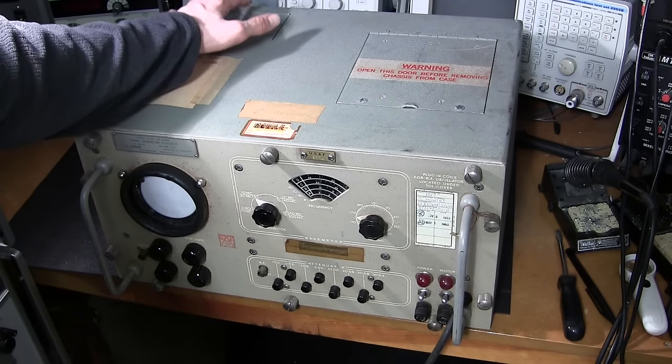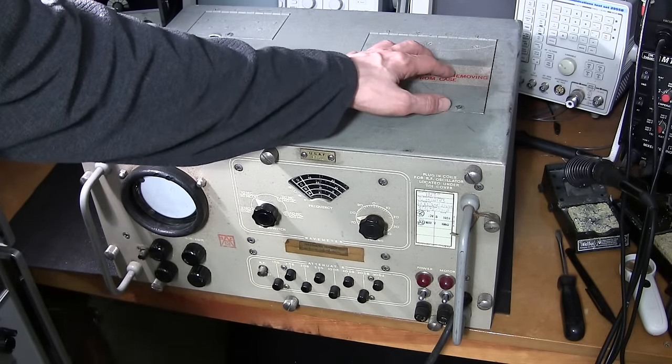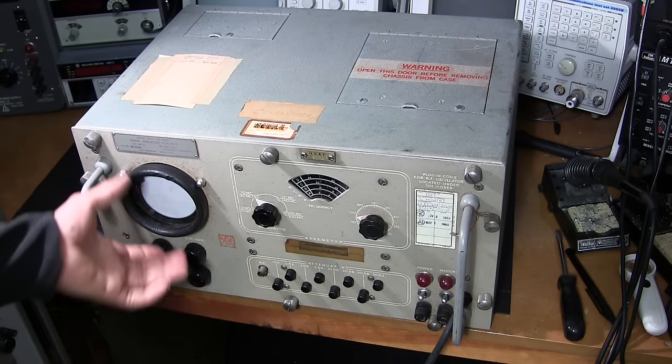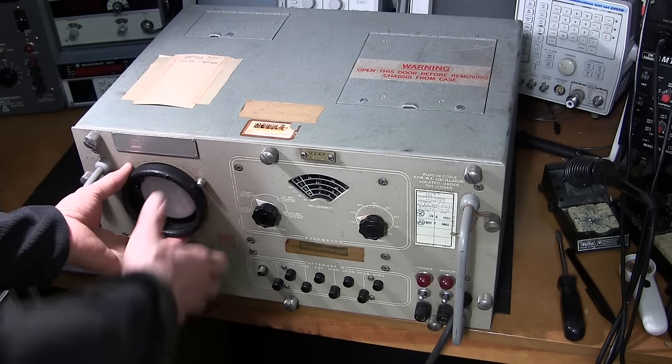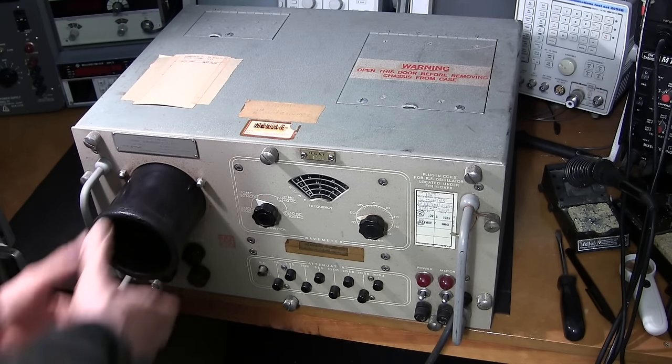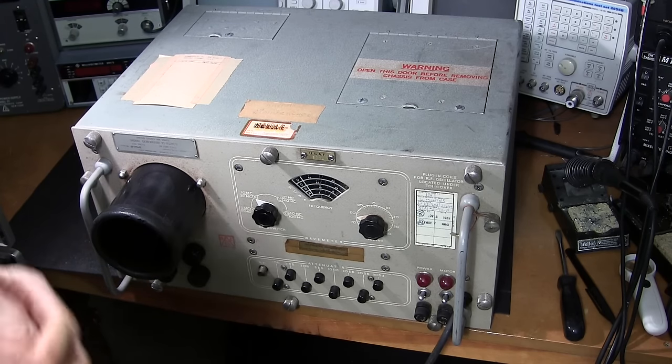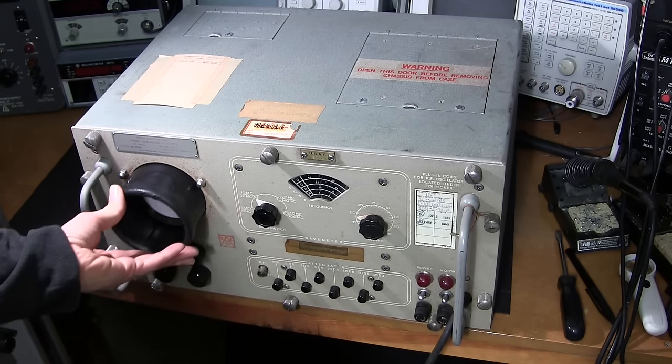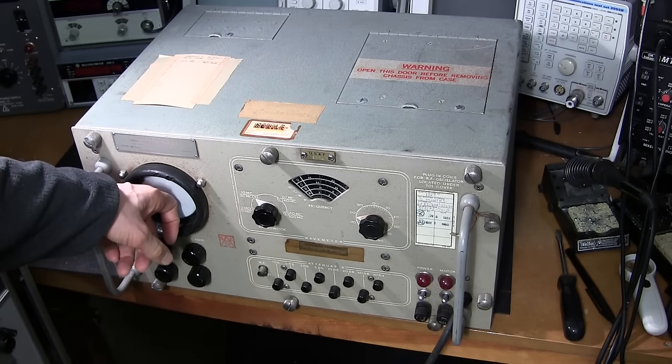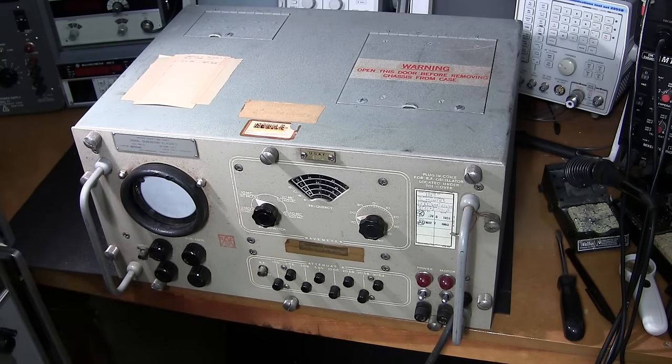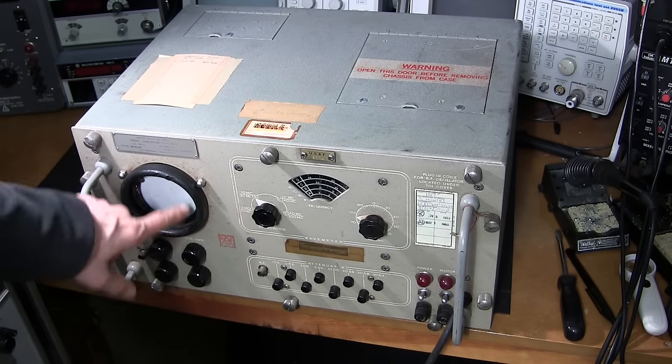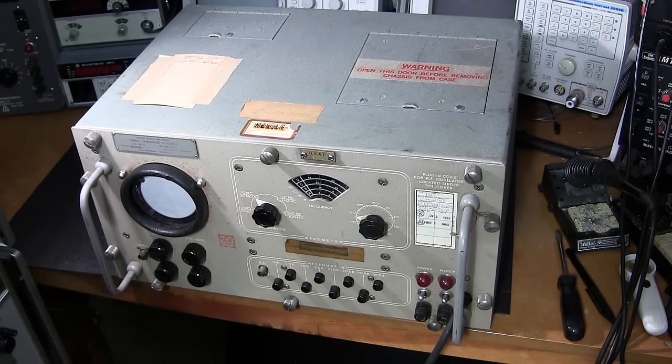Here's a bunch of service doors on the top, really what these are for is just adjustments inside. Here's a bezel that pulls out so if you're using this thing in bright daylight you can pull this bezel out so that it doesn't cause any issues with reading what's on that CRT. These little CRTs were never really all that bright back in the day, so by having this bezel that pulls out you can shield the external light from interfering with what you're looking at on this screen.